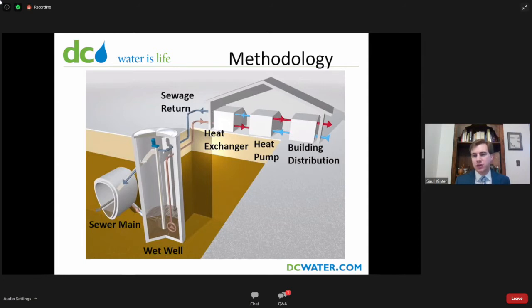So the heat exchanger is closed. There's no direct contact between the sewage and any of the actual clean water. And then conditioned clean water goes into a heat pump and the building farther down the line. The sewage then goes back, picks up the screenings, and goes straight back to the sewer, either colder or hotter, depending. So the end result is that we have warmer sewage in the summer or cooler sewage in the winter, and we've extracted that energy to feed the building.